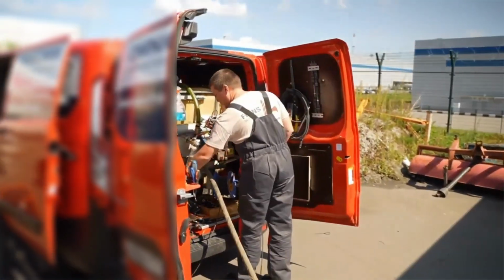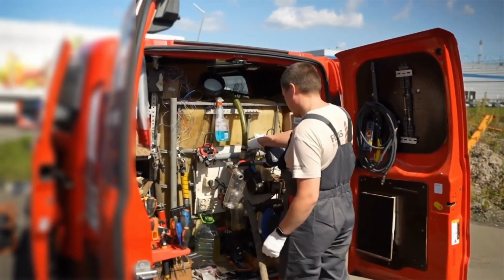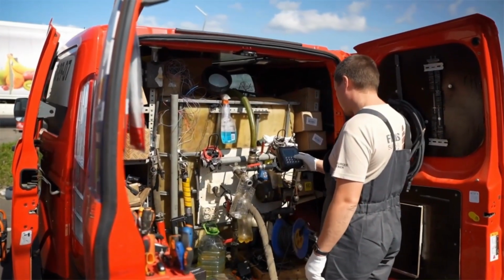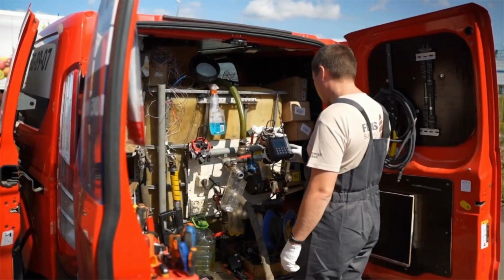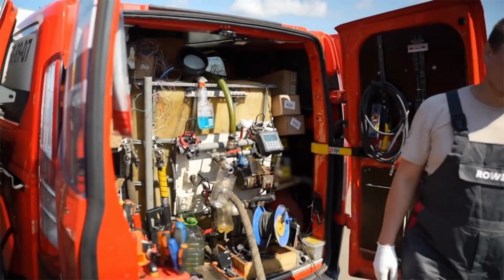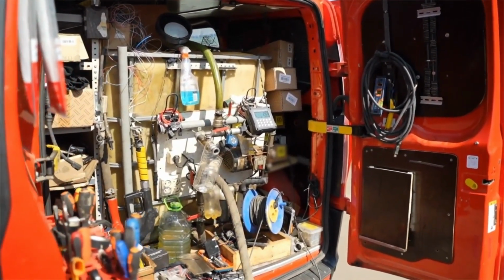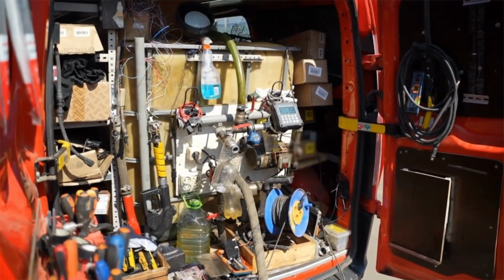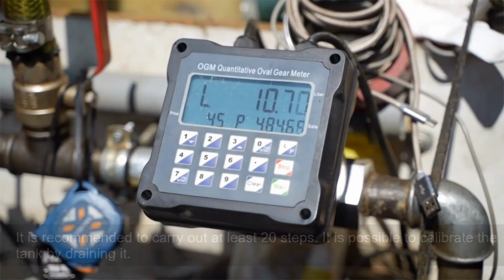Calibration of the fuel tank is refueling the tank from empty to full, following a certain refueling step, and recording the Omnicomm LLS sensor's readings in the calibration table. It is recommended to carry out at least 20 steps. It is possible to calibrate the tank by draining it.